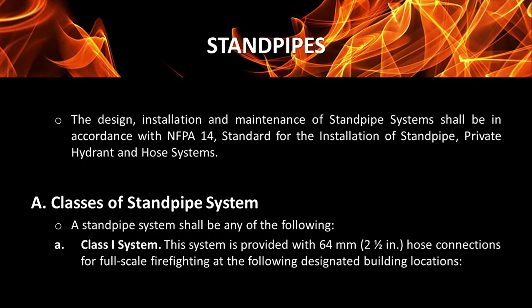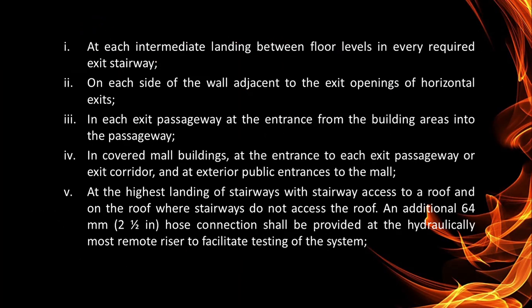Next, classes of standpipe system. A standpipe system shall be any of the following. First is the Class 1 system. This system is provided with 64 mm or 2 1/2 inch hose connections for full-scale firefighting at the following designated building locations. First, at each intermediate landing between floor levels in every required exit stairway. Second, on each side of the wall adjacent to the exit openings of horizontal exits. Third, in each exit passageway at the entrance from the building areas into the passageway. Fourth, in covered mall buildings at the entrance to each exit passageway or exit corridor, and at exterior public entrances to the mall. Fifth, at the highest landing of stairways with stairway access to a roof, and on the roof where stairway do not access the roof.